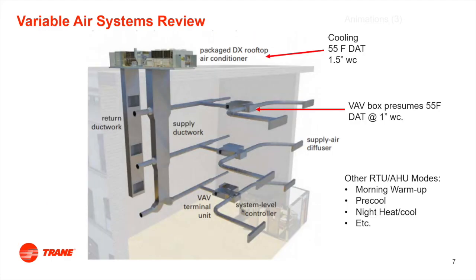Now, I'm going to back up to that slide we were just looking at before to talk about this. Now, let's say that this one on the bottom floor needs heat in the middle of the night. And what if there's 50 VAV boxes on this particular air handler, but only one of them, this one down here that has all the glass, needs heat?